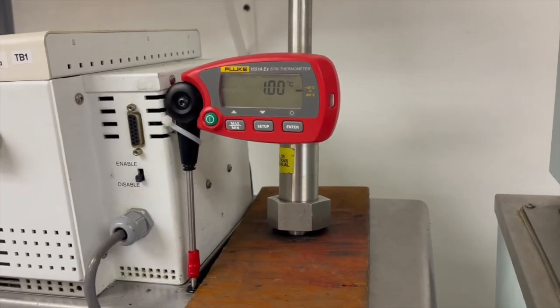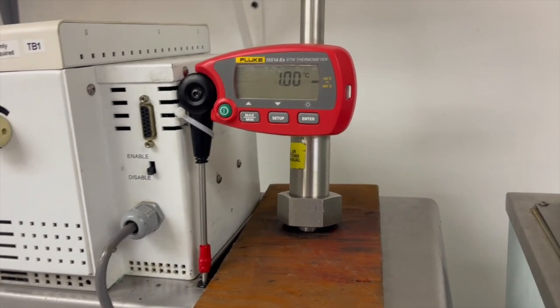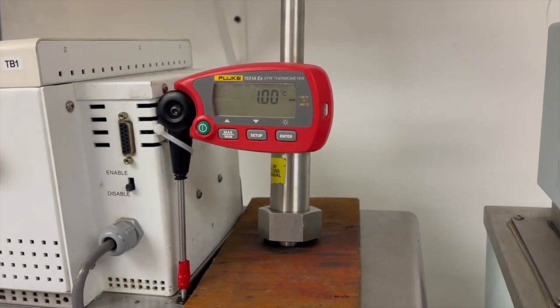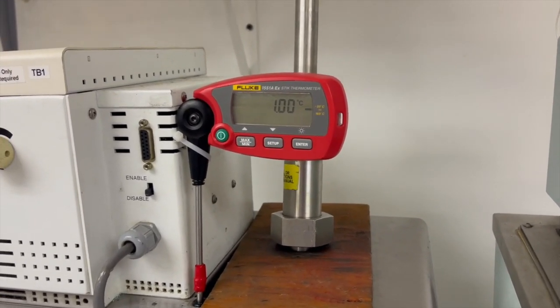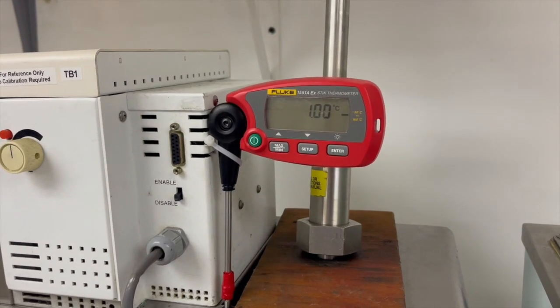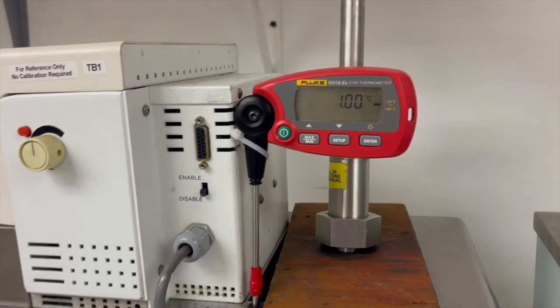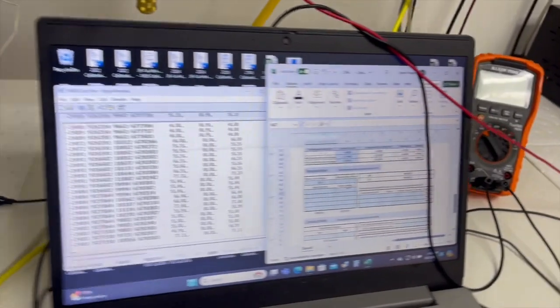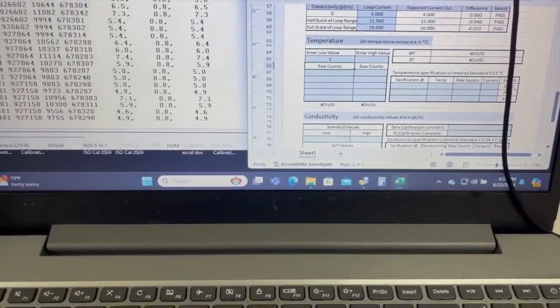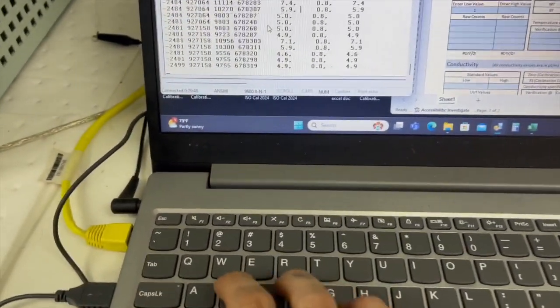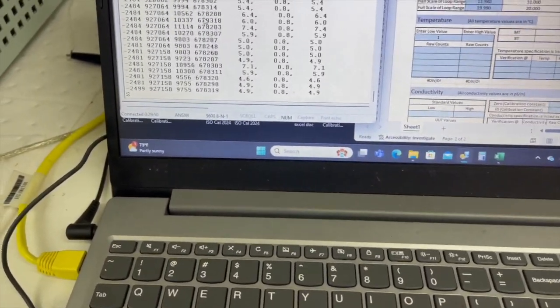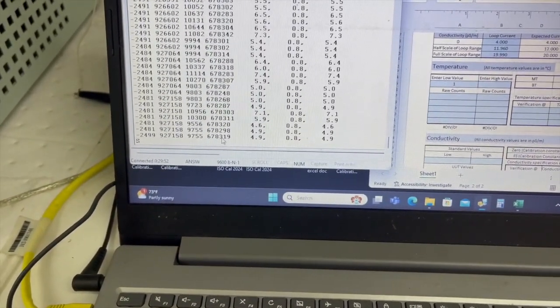So once you've waited 30 minutes, you come back and you want to check what the sensor counts are in order to calibrate it. So you can see here the temperature probe is at 1.00 degrees C. So we plug that in here, 1.00. And now we're going to get the temperature counts. So over here, and hit capital S to stop it from scrolling.